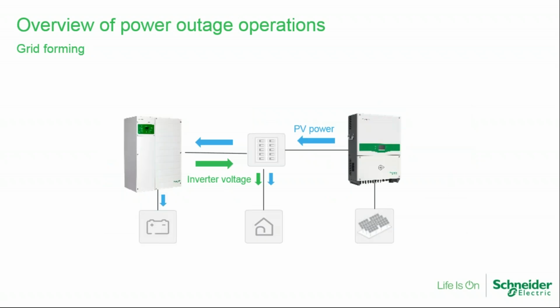When you have a power outage, then the XW turns on, seamlessly, basically. So likelihood is that the PV inverter will never even see an interruption in power, and it will then form the grid from the batteries, and the PV inverter will continue to operate. However, it has no way to sell power back to the grid. So whatever surplus power is created is backfed through the inverter and is used to charge the battery. Well, that's all well and good until the batteries become fully charged.